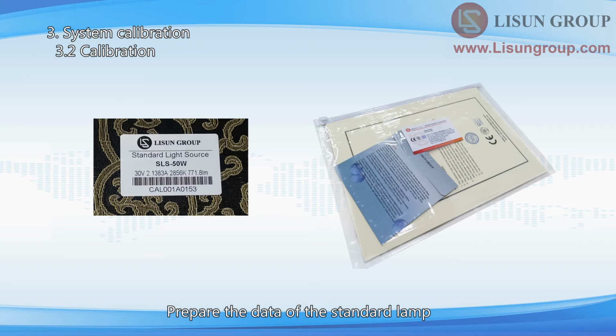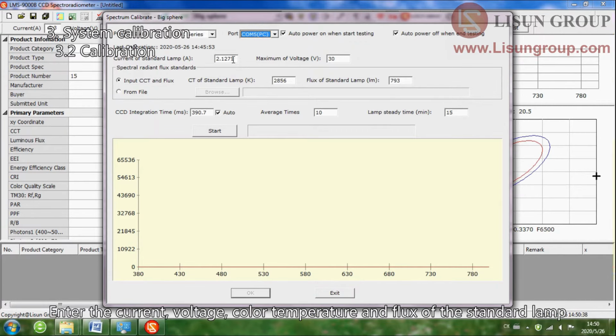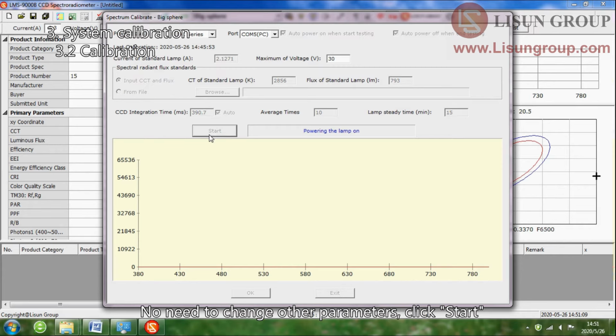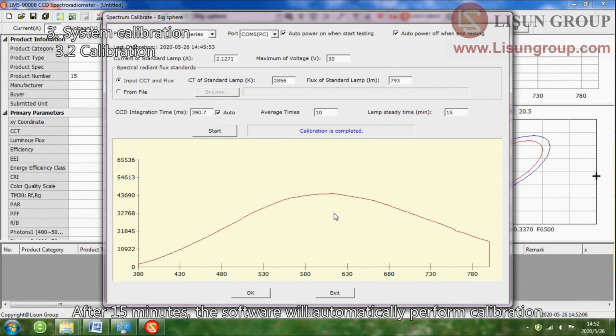Prepare the data of the standard lamp. The relevant data is on the lamp box and calibrate certificate. Enter the current, voltage, color temperature and flux of the standard lamp. Input 15 minutes for preheating time. No need to change other parameters. Click Start. The software enters a 15-minute countdown. After 15 minutes, the software will automatically perform calibration.